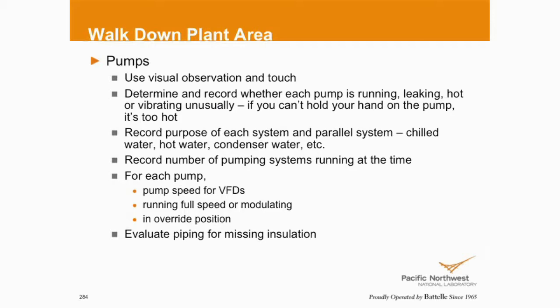Insulation on piping, look for that. Don't assume that you don't have a problem. Again, that's where the infrared camera can come into play. We see a lot of mechanical rooms where people go through and paint everything black or everything white. All the piping looks pretty, but now if I've got uninsulated steam or hot water or condensate lines, I'm not really thinking that way because I'm just seeing everything painted the same color. Or if I go into a building and there's no drop ceiling, it's right up to the roof deck above me or the floor above me. We see a lot of buildings with black, because, hey, we'll hide it. Well, until I start looking up there, I may miss piping that was not insulated or was removed.